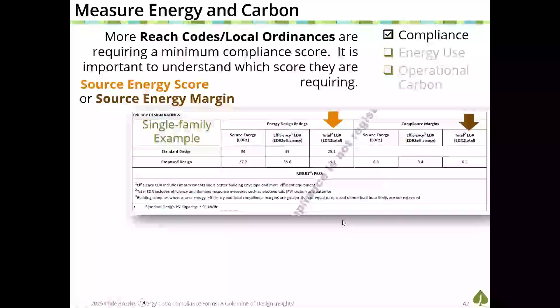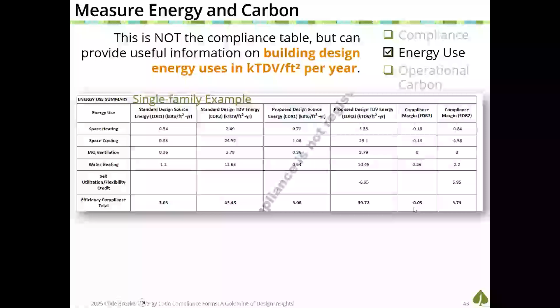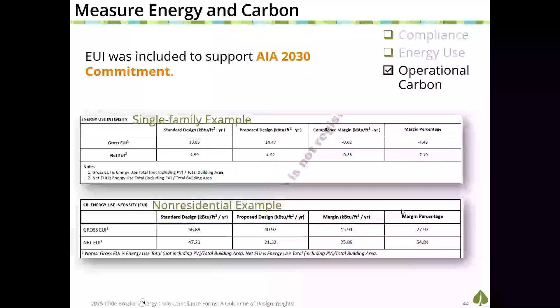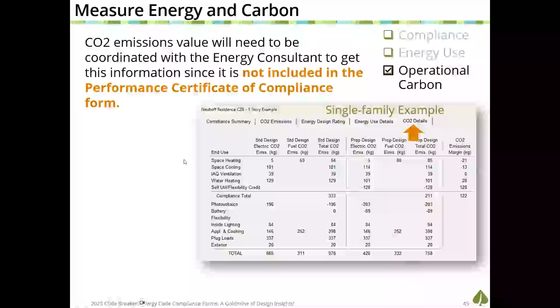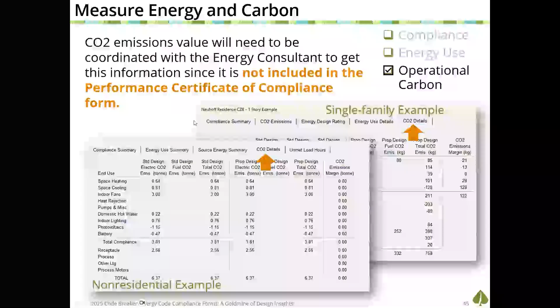What we get out of using the performance approach is measurements against the energy code. We have the source energy metric, and we also have energy use summaries, which is just the actual energy use. We also have kBTU per square foot per year. Within the software itself, we have CO2 measurements. So there's so much that's included. Now, the CO2 doesn't show up in the certificate of compliance, but it's something you can ask to have given to you by the person who is doing your calculations.